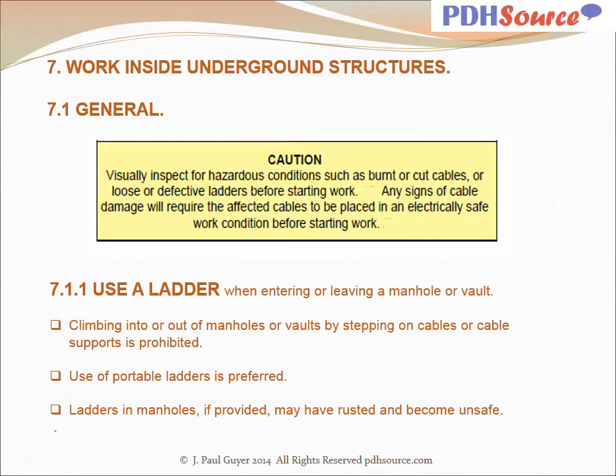Caution. Visually inspect for hazardous conditions such as burnt or cut cables or loose or defective ladders before starting work. Any signs of cable damage will require the affected cables to be placed in an electrically safe work condition before starting work. Use a ladder when entering or leaving a manhole or vault. Climbing into or out of manholes or vaults by stepping on cables or cable supports is prohibited. Use of portable ladders is preferred. Ladders in manholes, if provided, may have rusted and become unsafe.